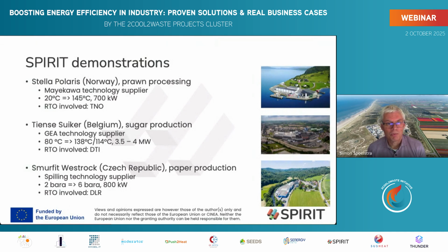We will replace this with a heat pump concept supplied by Mayekawa from Belgium, the European office. It's a cascaded system, consisting of 2 heat pumps in cascade. The first heat pump takes heat from around ambient temperature, which is actually condenser heat from the existing refrigeration system, dumping heat at about 20 degrees. That is upgraded with an ammonia heat pump to 80 degrees, and then a pentane heat pump on top upgrades it further to the steam required for the prawn processing, the cooking of the prawns.